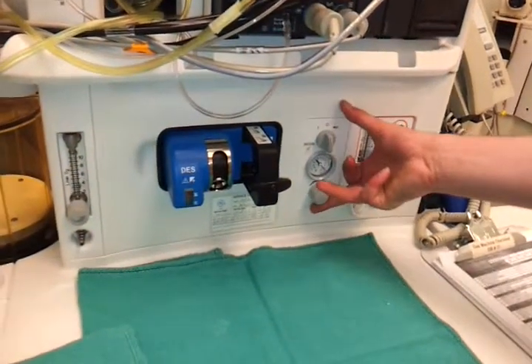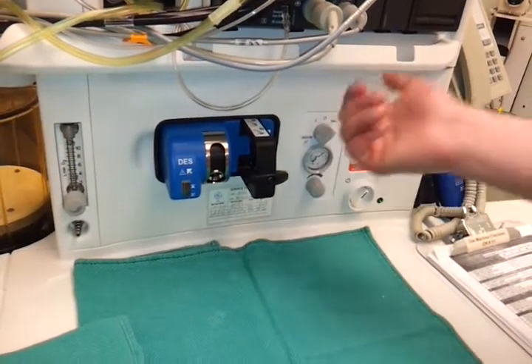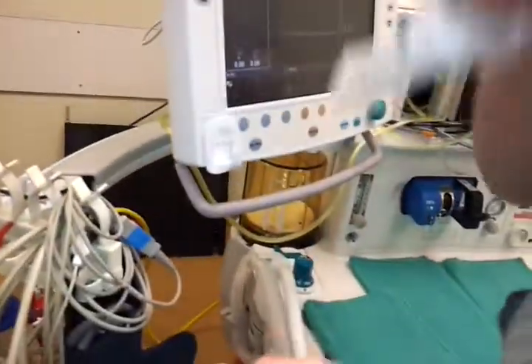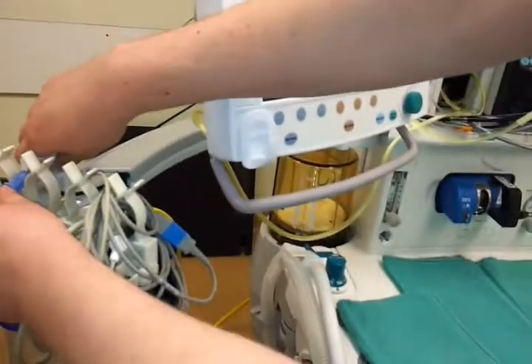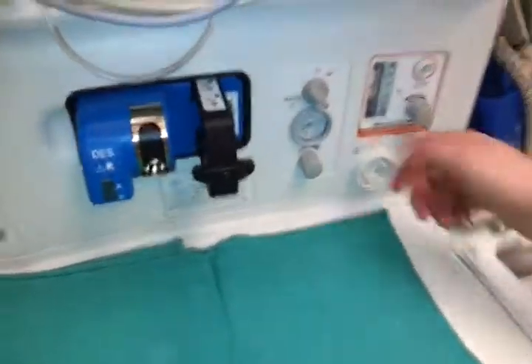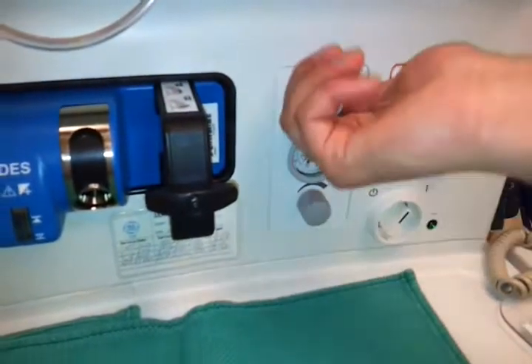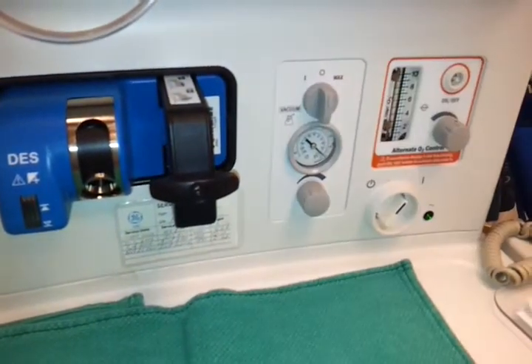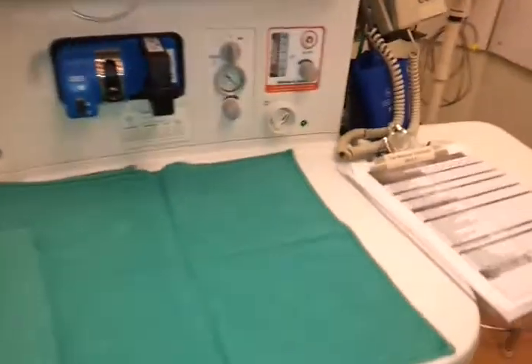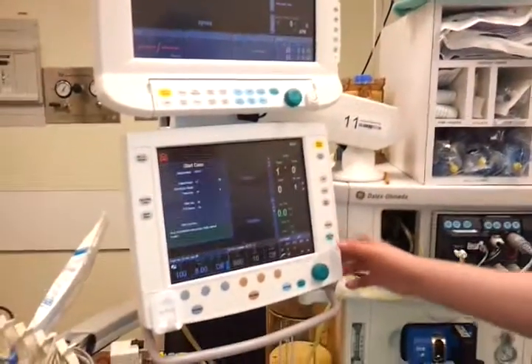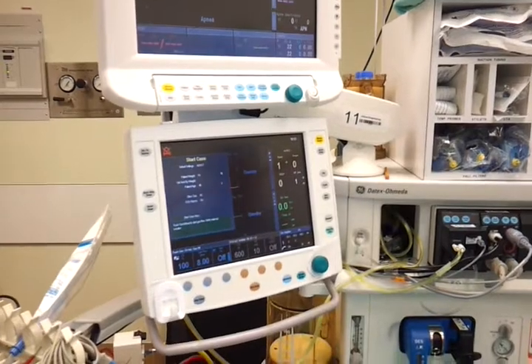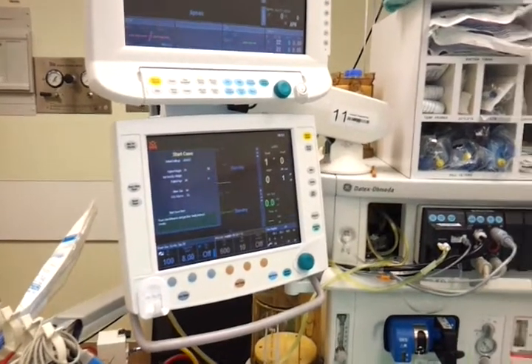So the suction stuff is right here. And you can put it on max, you can hear it, but it's always a good idea to put on some gloves. So the suction's adequate. You can put it on there and adjust whatever suction you want, but most of the time it's just going to be Yankauer. And that's pretty much it. If the case doesn't start in an hour, you can turn off the monitors. If not, you can just leave it in standby, just like this. That's pretty much it for the gas machine check.